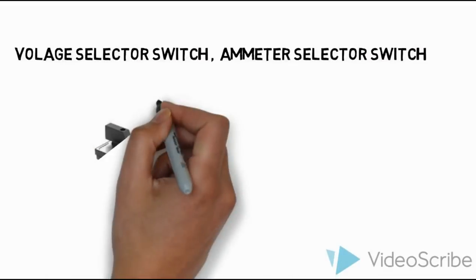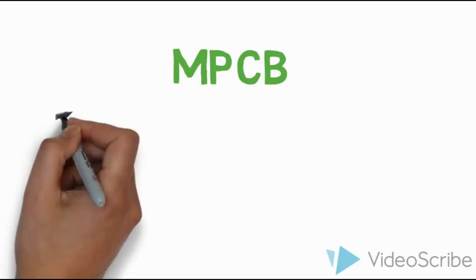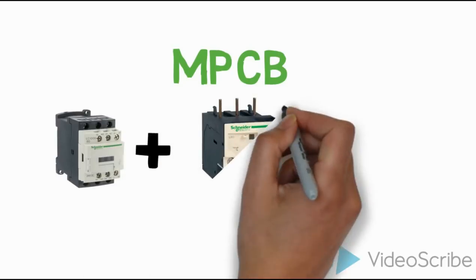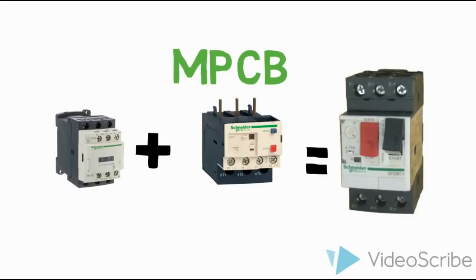Next is the MPCB — Motor Protection Circuit Breaker. MPCB combines a circuit breaker, contactor, and overload relay into one device. It provides all-around protection, on-off switching, trip indication, and trip function. The contactor handles on-off purposes and motor protection. A standard circuit breaker is not the same as an MPCB.